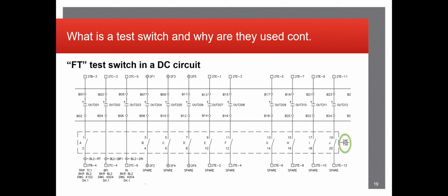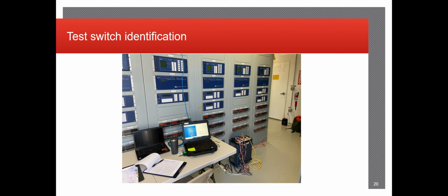We have multiple identifiers as well to the right here in the green circle. That is usually a client-specific identifier labeling the location on the panel itself. So in this case, we would assume and verify that it's going to be panel 2 in the AE spot, and as well as this is going to be test switch 6. As said previously, they identify the specific test switches as well, A, B, C, D, and odd and even numbers.